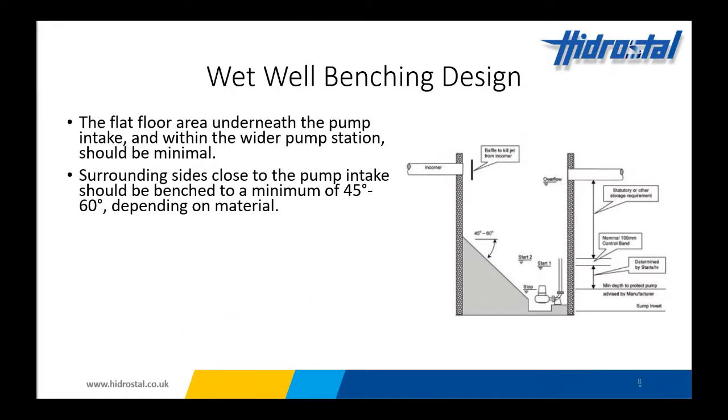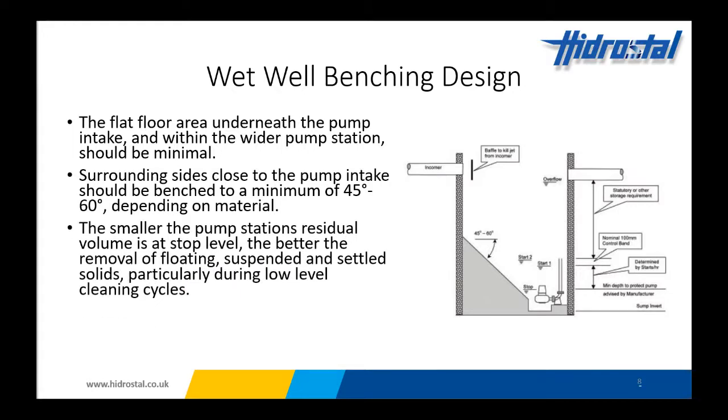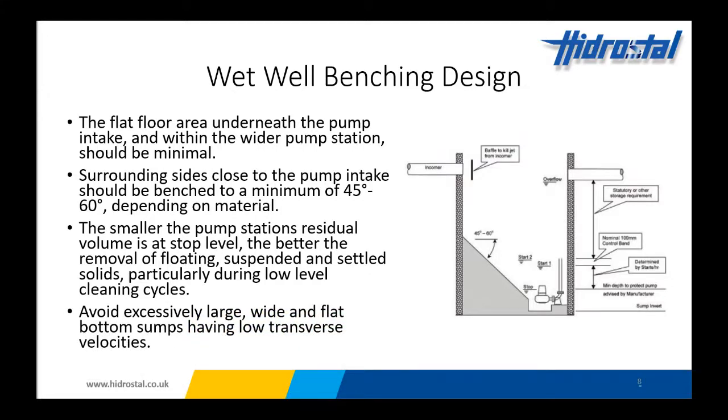Plastic, probably 45 degrees. And the smaller the pump station's residual volume is at this low level stop, the better the removal of your floating, suspended and settled solids during the cleaning cycles. So one thing to really avoid is excessively large, wide, flat bottom sumps, as you've got no transverse velocity to do any cleaning. So things will build up.